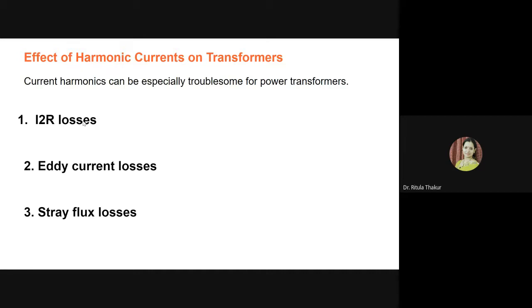Then the second kind of losses are eddy current losses. These eddy current losses are due to the higher order currents in the core of the transformer, and these currents create an abnormal temperature rise. What will happen because of the temperature rise? The increased temperature accelerates the loss of insulation and can ultimately lead to a shorter lifespan of the equipment. And the third type of loss is the stray flux loss, which occurs in the core, clamps, and other iron components of the transformer. These stray losses also increase the oil temperature.